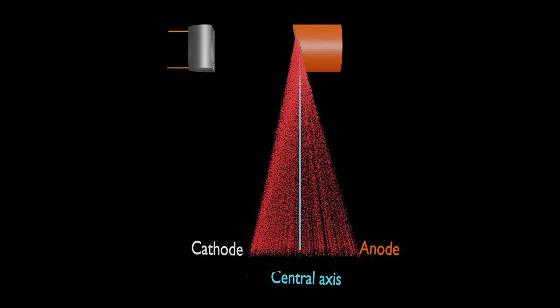Let us analyze intensity of x-ray across anode-cathode direction. What is observed is the radiation intensity on the cathode side of an x-ray field is greater than that on the anode side.